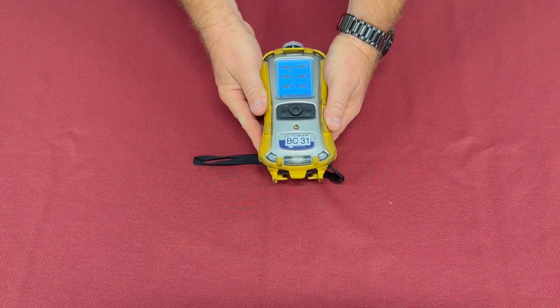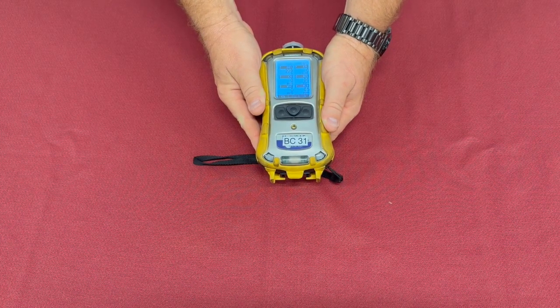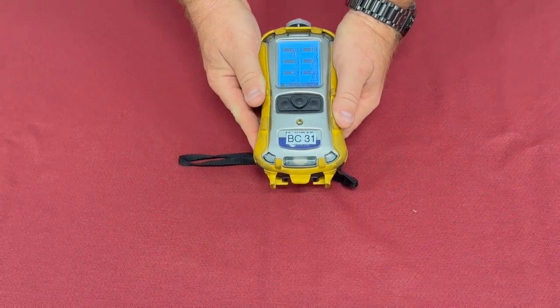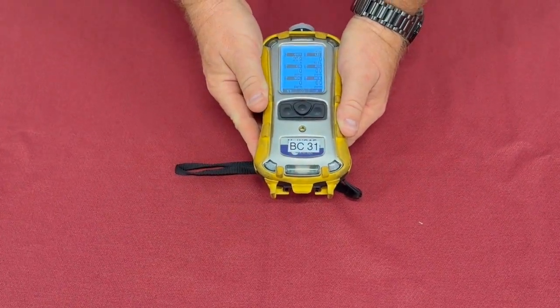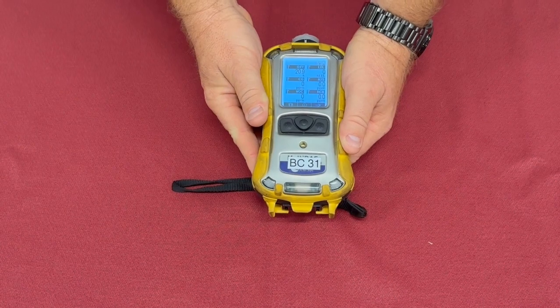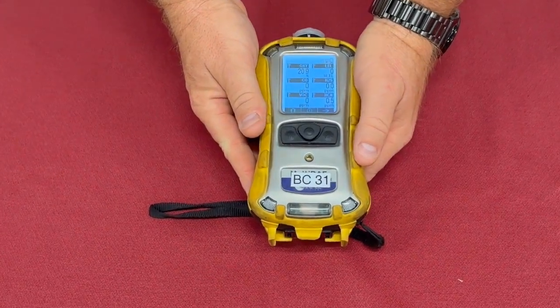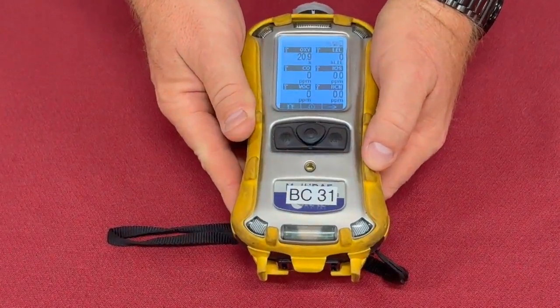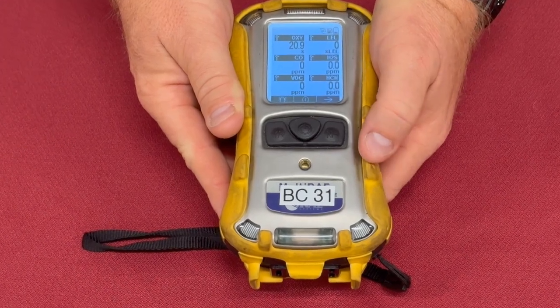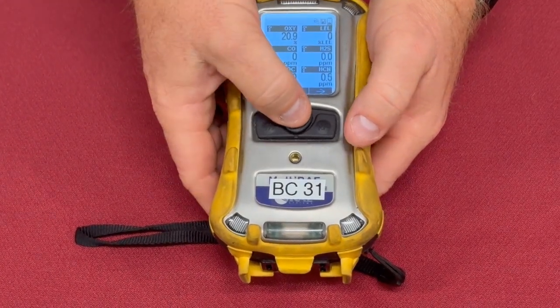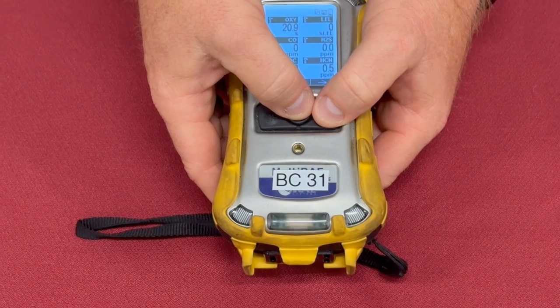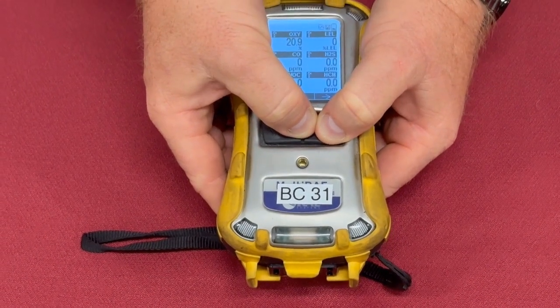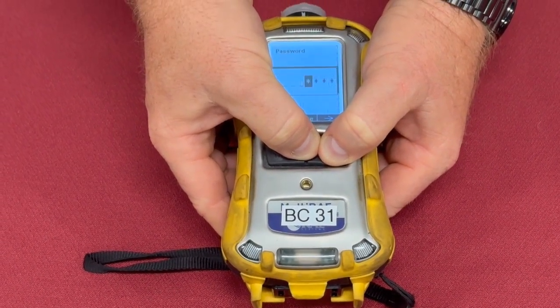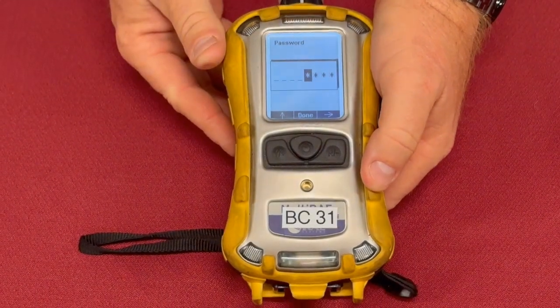All right, the meter goes into its normal mode now. So if everyone has done all of their checks appropriately, this is where you will find the meter after the fresh air setup. To get into the menu and actually do a calibration, all you do is press the center button and the right button at the same time, hold them until the password screen comes up.